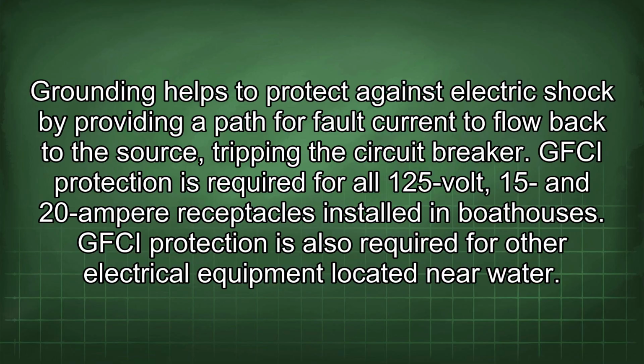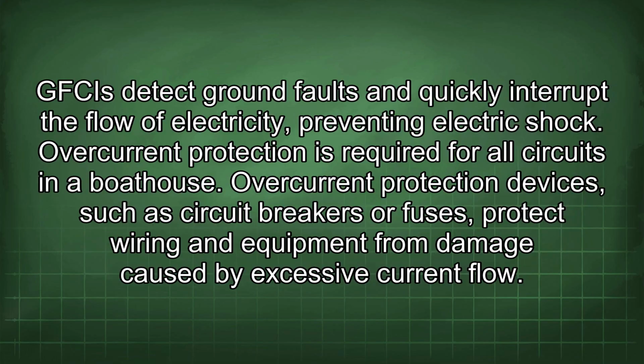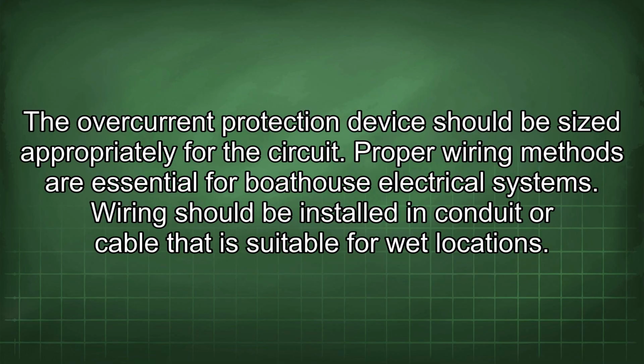GFCI protection is required for all 125 volt, 15 and 20 ampere receptacles installed in boathouses. GFCI protection is also required for other electrical equipment located near water. GFCIs detect ground faults and quickly interrupt the flow of electricity, preventing electric shock. Overcurrent protection is required for all circuits in a boathouse. Overcurrent protection devices, such as circuit breakers or fuses, protect wiring and equipment from damage caused by excessive current flow. The overcurrent protection device should be sized appropriately for the circuit.